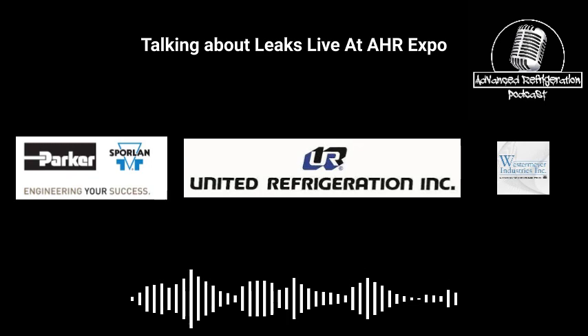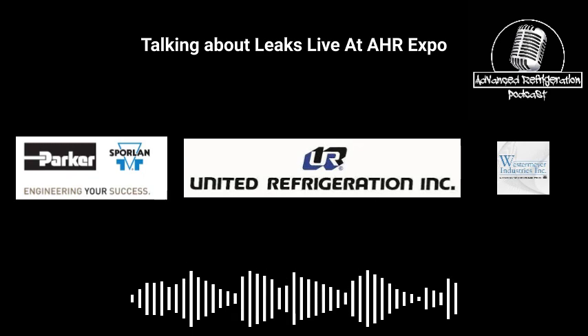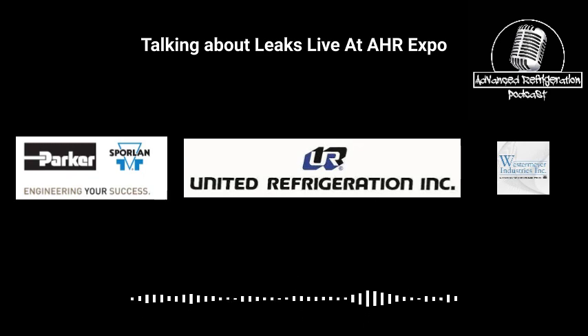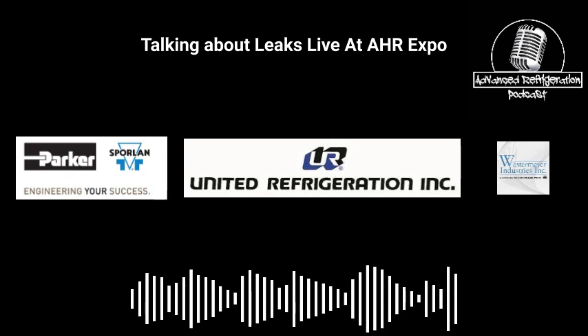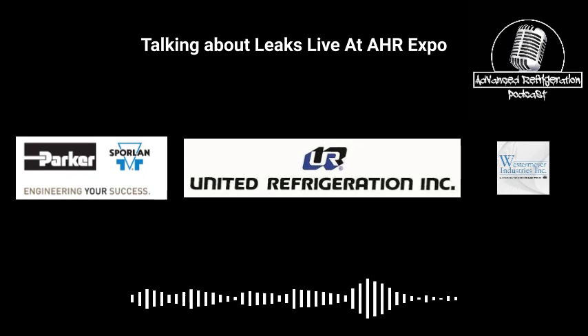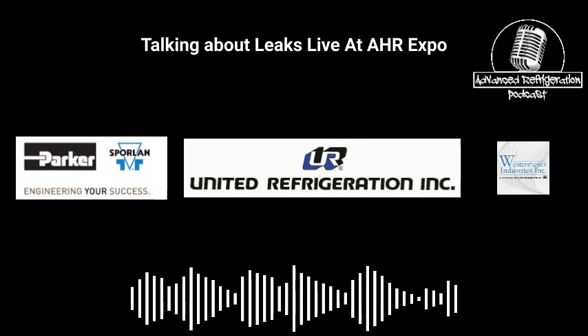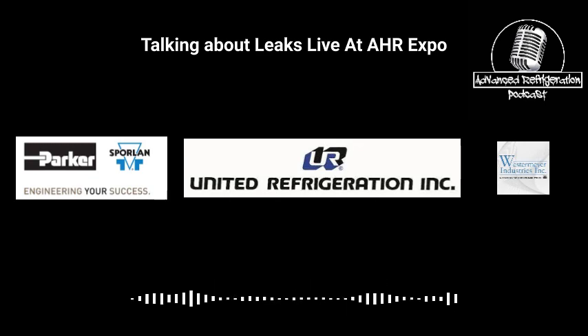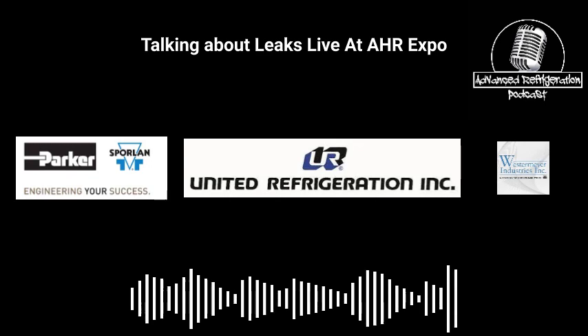Yeah, I mean, in all leak detectors, it doesn't matter who the brand is, they're zeroing out to what they think is a zero. It's not a true zero. So that's where you run into this issue: you could have a building that is so saturated with CO2 that the leak detector doesn't work right. Very true. Well, hold on, let me ask you a question. Before you tell the story, did you start up the leak detector outside before you brought it inside? Tried both. Yeah. Wow. Yeah, we tried both.